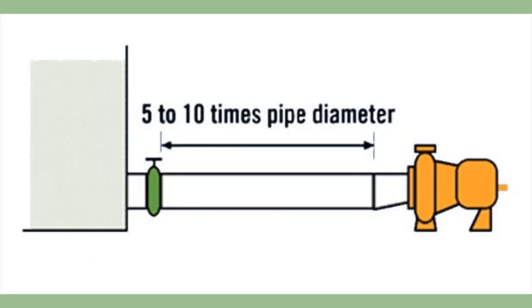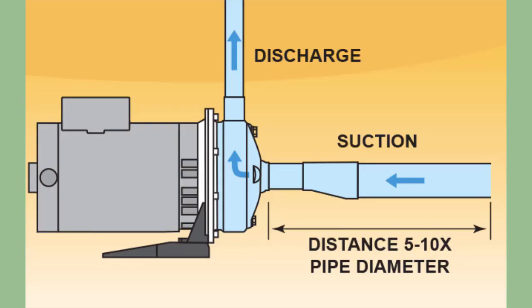Number one, keep suction piping as short as possible. Include a straight run pipe length equal to five to ten times the pipe diameter between the pump inlet and any obstruction in the suction line.